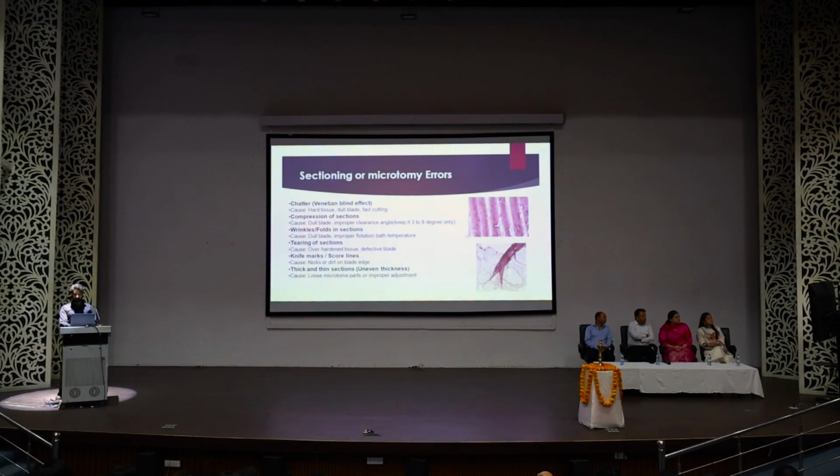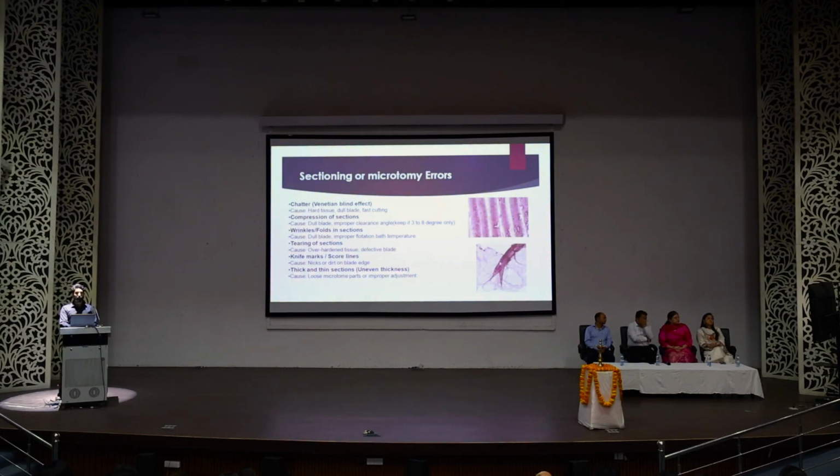You can see here an image with a fold. This has happened because of low temperature in the tissue flotation bath.